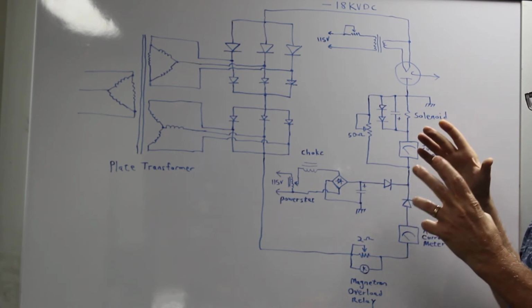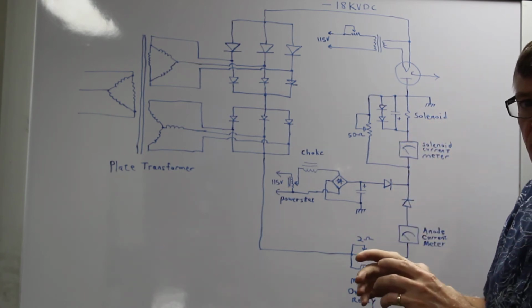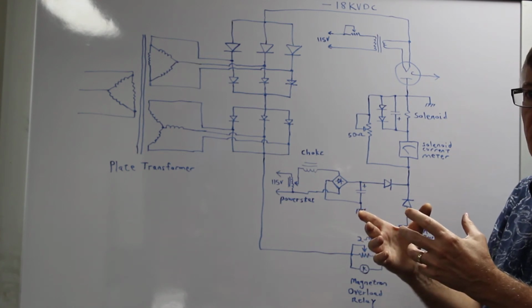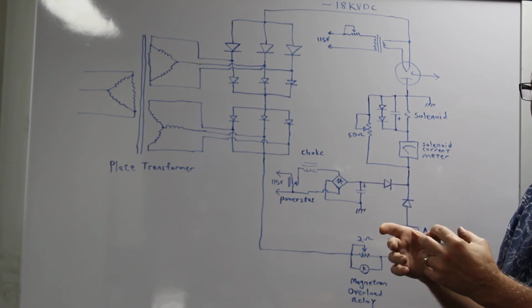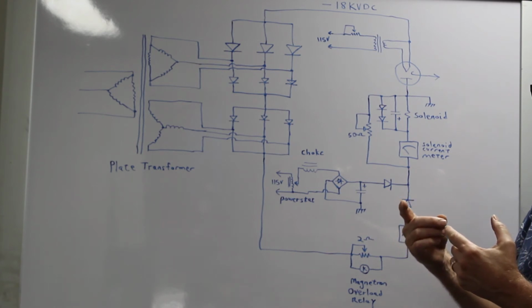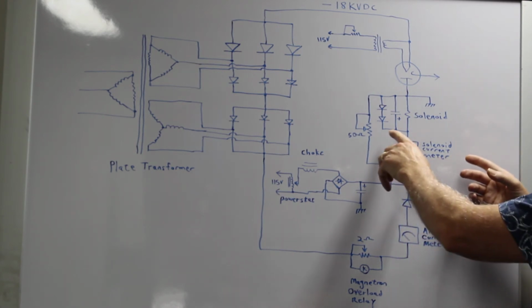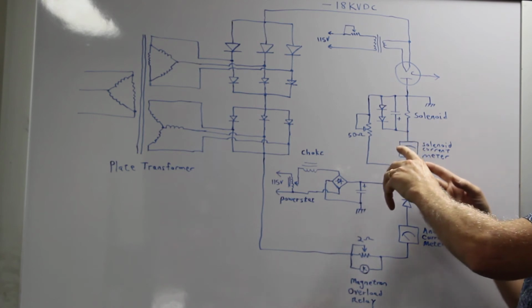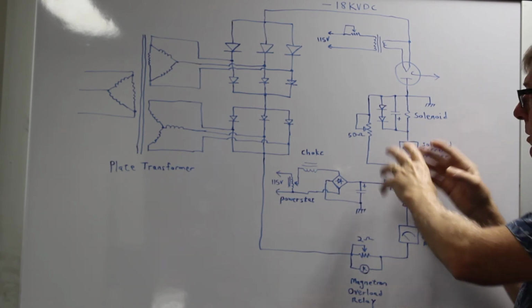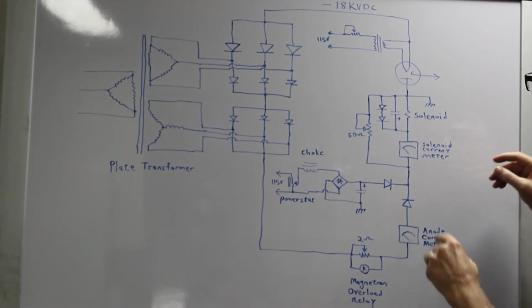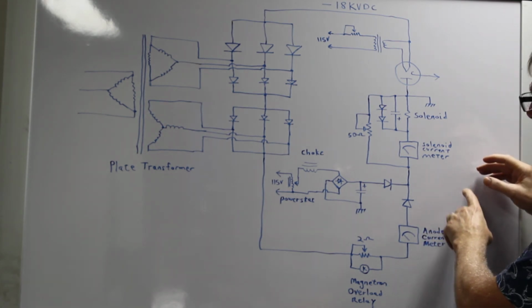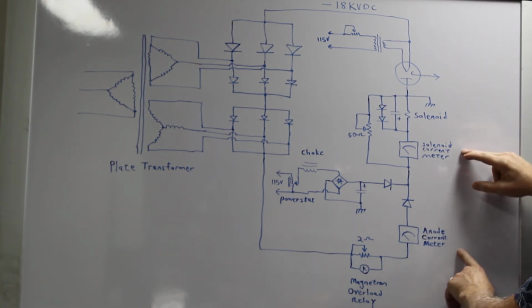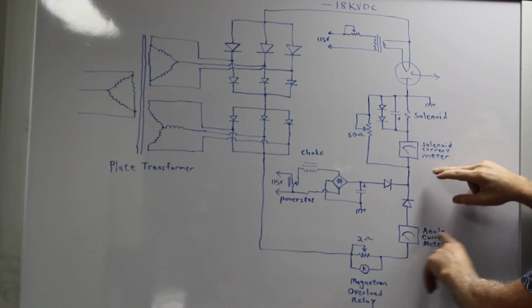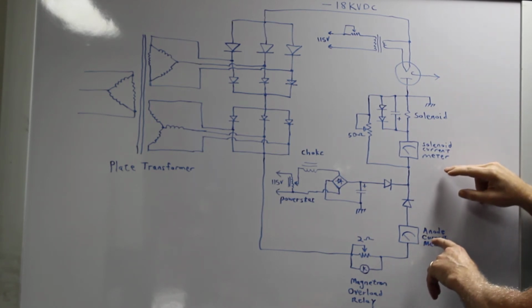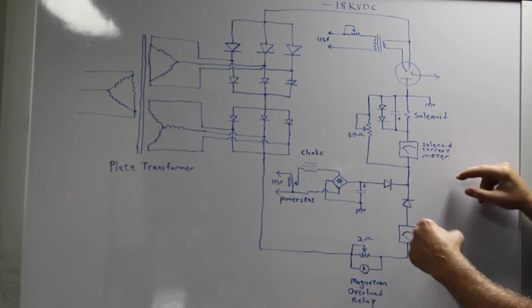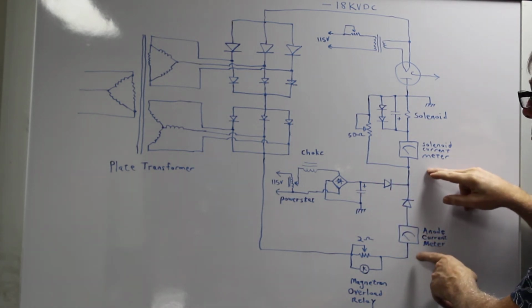Because the magnetic field that's generated there will collapse around the coil, which the solenoid basically is, just a large coil of wire, it will induce a large voltage in the opposite polarity of the normal running voltage. And so these diodes and the capacitor absorb that energy and dissipate it safely without injuring the other components. You'll also see that we have an anode current meter here and a solenoid current meter here. Some transmitters, these aren't actual panel meters, sometimes they're a shunt that drives a PLC input or something like that, but they're in the same locations.